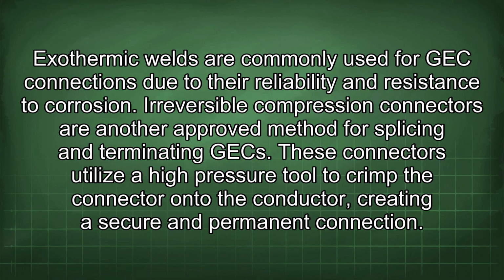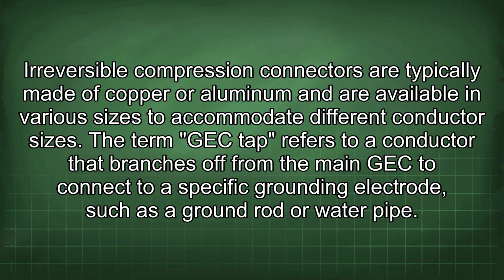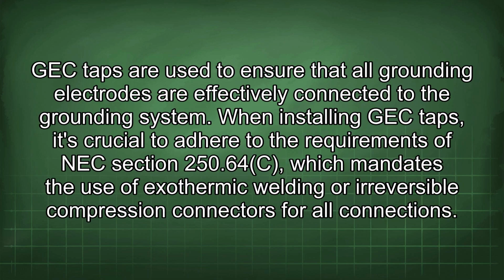Irreversible compression connectors are another approved method for splicing and terminating GEC. These connectors utilize a high-pressure tool to crimp the connector onto the conductor, creating a secure and permanent connection. Irreversible compression connectors are typically made of copper or aluminum and are available in various sizes to accommodate different conductor sizes. The term GEC tap refers to a conductor that branches off from the main GEC to connect to a specific grounding electrode, such as a ground rod or water pipe. GEC taps are used to ensure that all grounding electrodes are effectively connected to the grounding system.